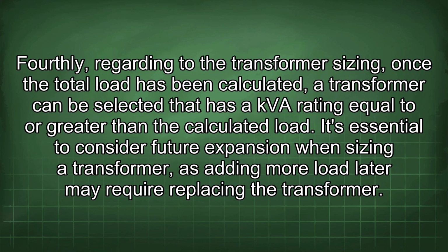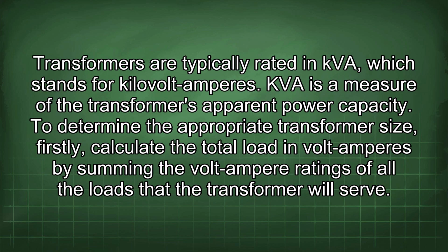Fourthly, regarding transformer sizing, once the total load has been calculated, a transformer can be selected that has a kVA rating equal to or greater than the calculated load. It's essential to consider future expansion when sizing a transformer, as adding more load later may require replacing the transformer. Transformers are typically rated in kVA, which stands for kilovolt amperes. kVA is a measure of the transformer's apparent power capacity.